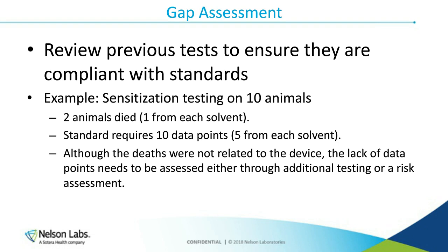If it had just been 1 solvent, we could maybe have addressed that with a risk assessment on that one animal. But because 1 died from each solvent, we're now down 2 data points. You really need to have 10 for it to be statistically appropriate, and based on the guidance document, we now no longer meet the guidance document. So we did recommend that additional testing should be performed, or a risk assessment based on previous clinical data, or some additional chemistry testing to predict the sensitization response.